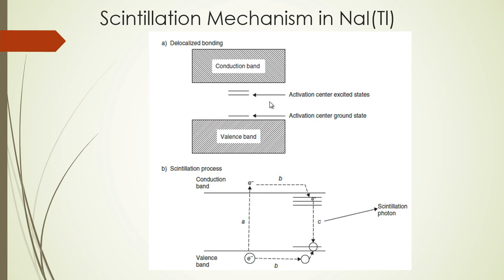This gives a photon of approximately 3 electron volts from the thallium-activated sodium iodide detector. For example, if a gamma ray from a cesium source at 662 keV imparts around 500 keV to an electron in the crystal, that electron causes many excitations and ionizations, sending many electrons to the conduction band. When all those electrons return to the ground state by this process, a large number of photons of about 3 eV are emitted, corresponding to the ultraviolet or blue range of the electromagnetic spectrum.